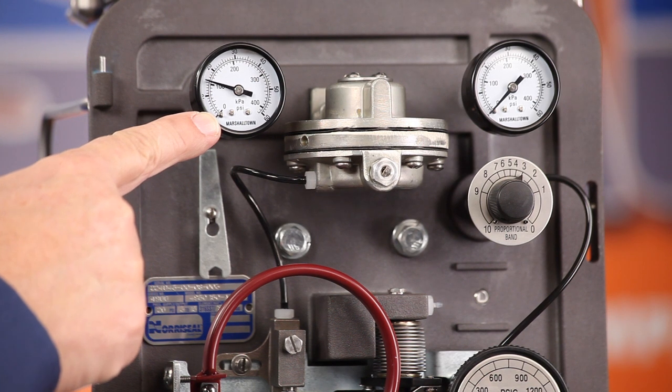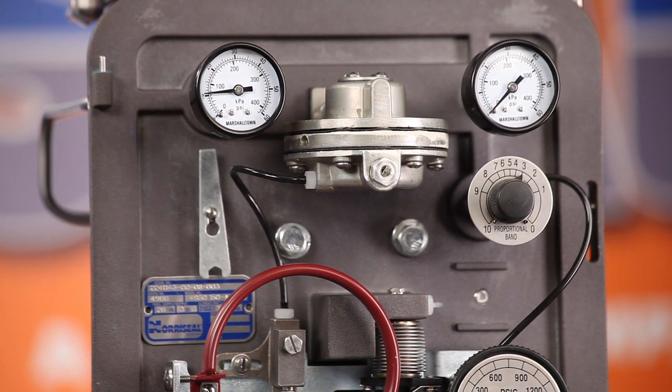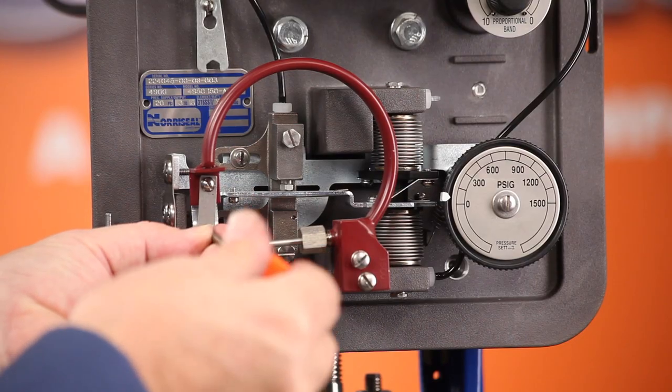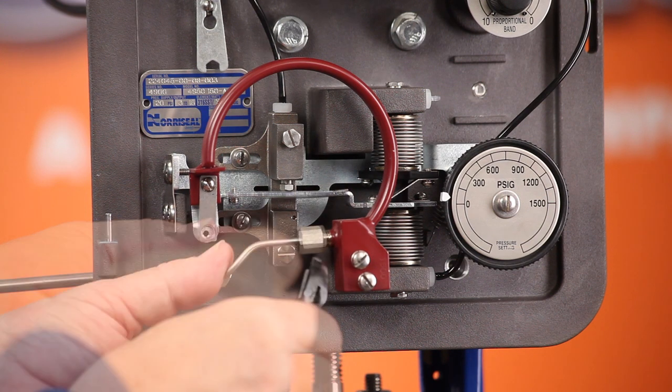To replace your Bourdon tubes, first you need to shut off the supply and control pressure inputs to the controller or transmitter. Remove the machine screw that connects the link and the bearing between the beam and the Bourdon tube.